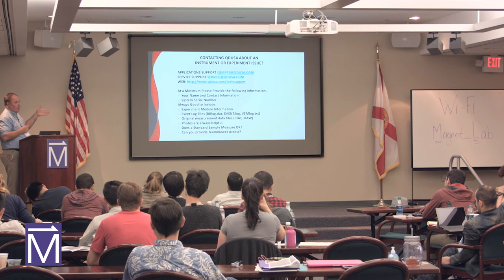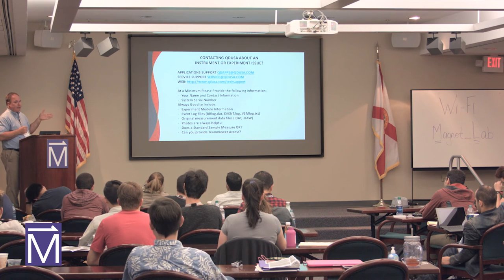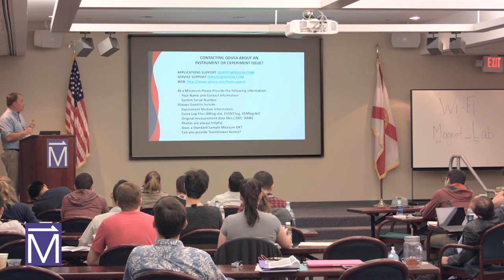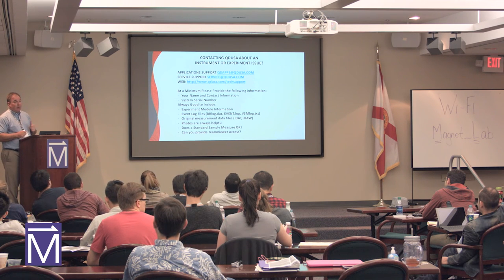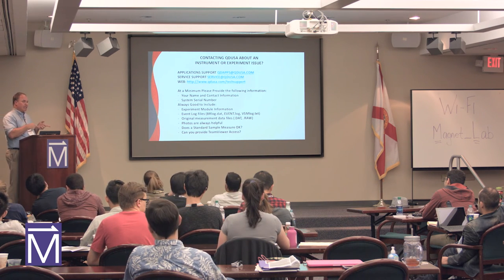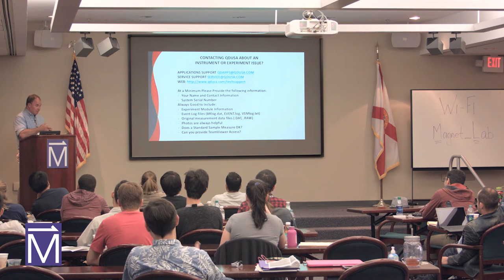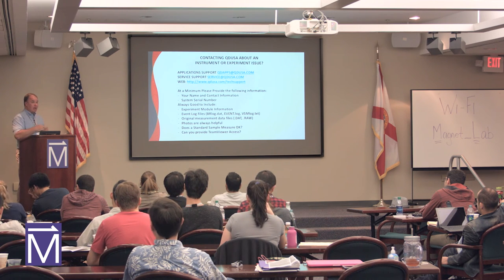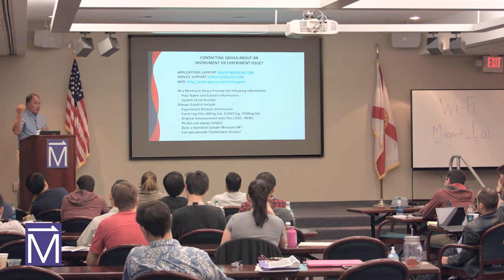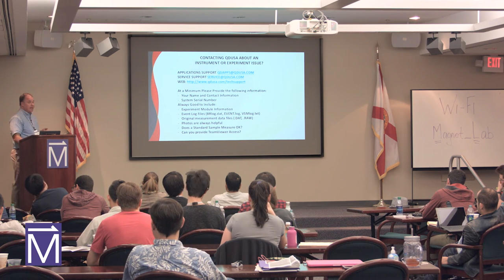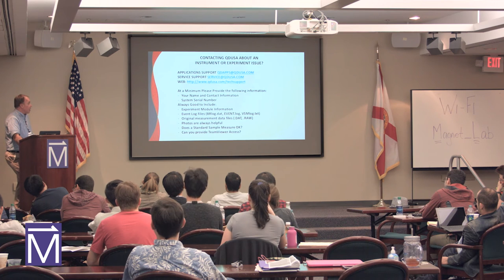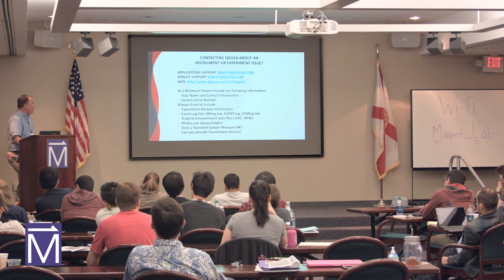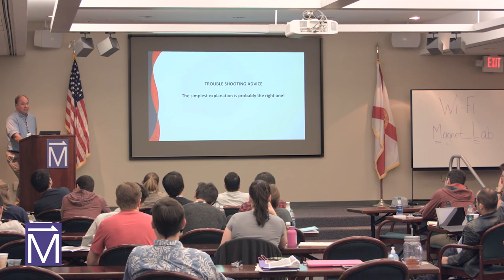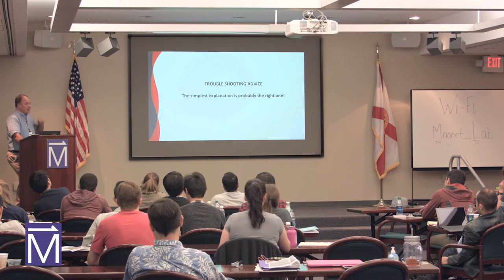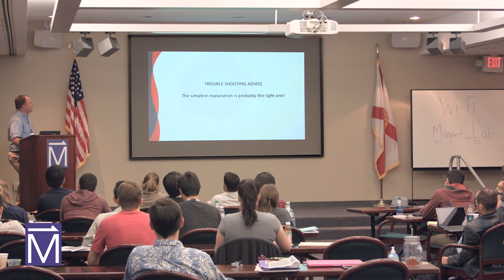On these instruments, it's always good to give us information on what you're doing. If you can give us the log file, it's great. Give us the serial number. We've got TeamViewer. The guys like to TeamViewer into your system, so we put that on every system and we'll come in and look at it. We've got guys in the service team that can just log in and they might be able to solve your problem in a couple of minutes if we have your name and number to call you back. The simplest explanation is probably the correct one. So that's probably a good way to do it if you're trying to troubleshoot things.